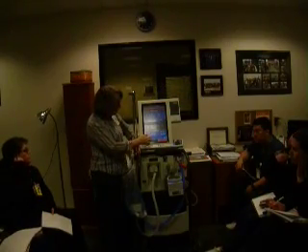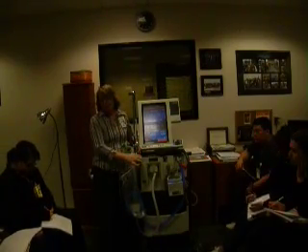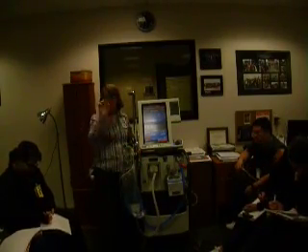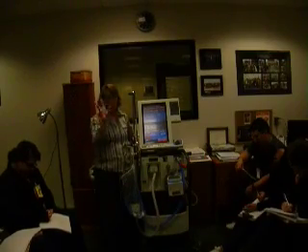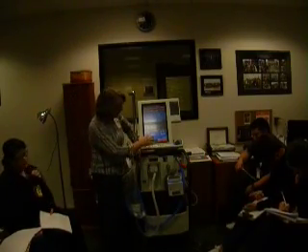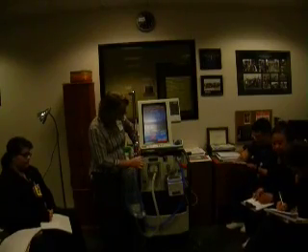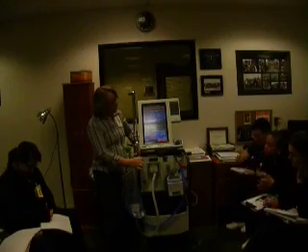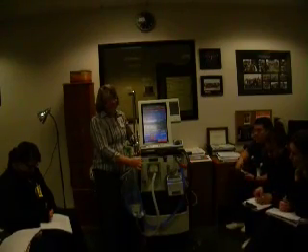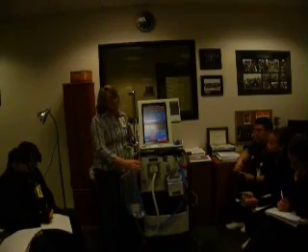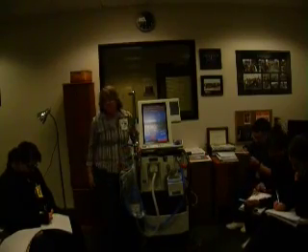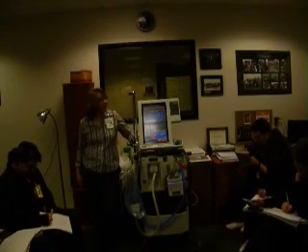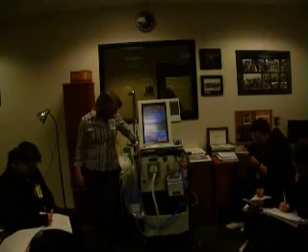Right. So we do the mode, and remember, there's two parts to every mode. We have to have the AC or SIMV, but then we have to have the volume or pressure component of it. Remember, it's not just one or the other; they go together. So we'll set that. Then, under mandatory type, you can do PC, pressure control, VC, which is volume control, and VC plus, which is this vent's version of PRVC.